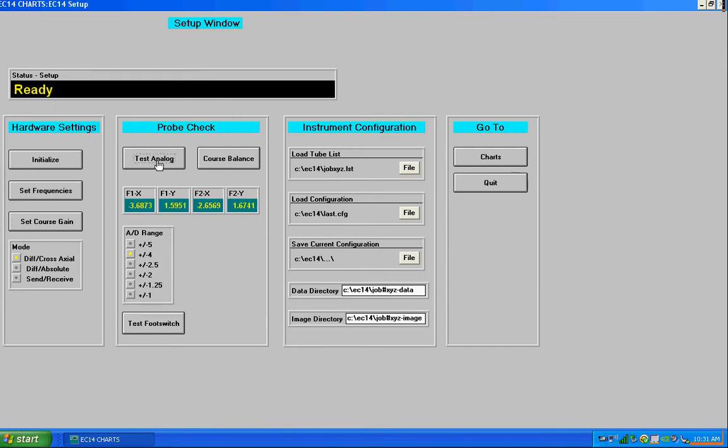So we can see we're at 3.6 on channel 1 and the A to D range is plus or minus 4. So I'm going to go ahead and change this A to D range to plus or minus 5 just to give us a little more headroom to operate this probe so that the probe doesn't saturate.